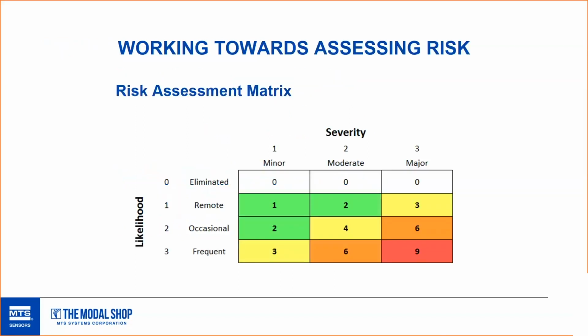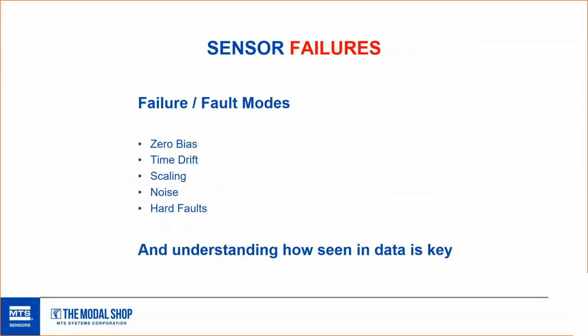The other major consideration towards understanding what sensor calibration intervals are appropriate for a test comes from investigating how likely the sensor, and really the entire measurement channel, is to experience an issue. Understanding failure modes, causes, and how issues are manifested and seen in data is really key, as well as often overlooked things like what happens in the sensor's life between calibration and test. So let's look over some likelihood of sensor failures. And again, for the sake of example, we may pick on accelerometers, but there's a great paper that we'll reference in our email follow-up to this that we love, that discusses a lot of types of sensors and their primary faults.